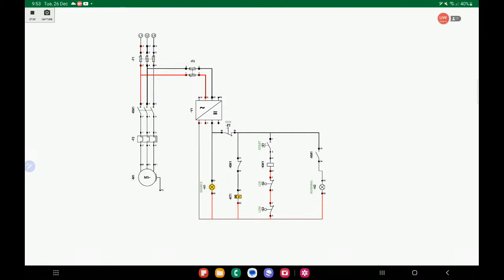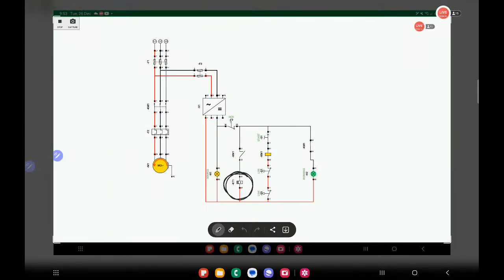So if I will start the system, now it's retracting, no? The lifeboat now, electrical motor is running. So KM1 is activated, KT1 is deactivated. So this KT1 is deactivated because of this braking contact. So this is okay, this is okay. So lifeboat is being retrieved.